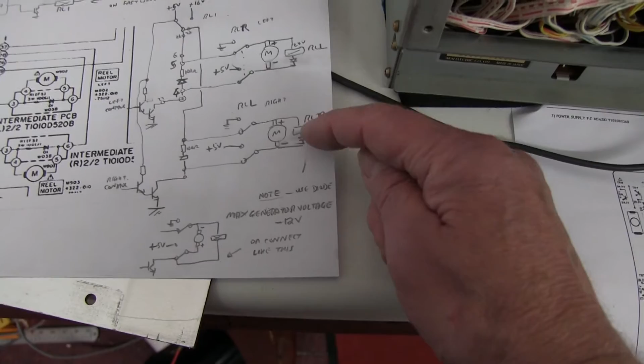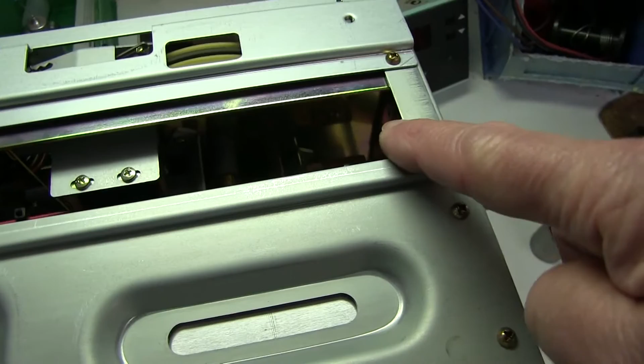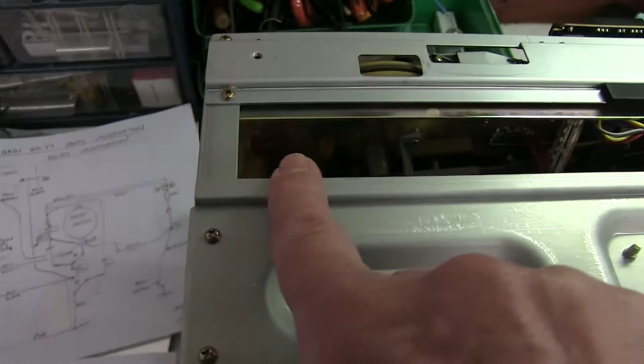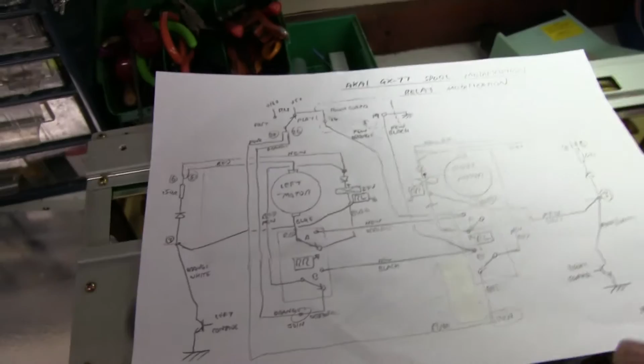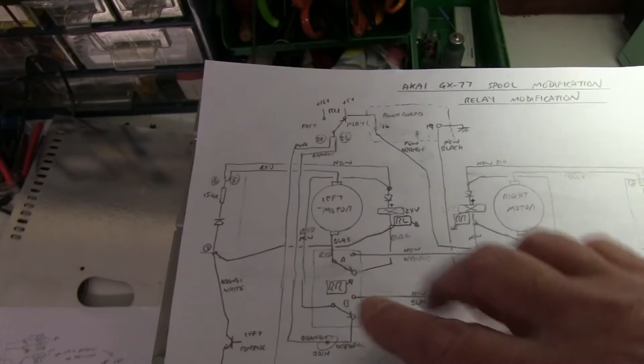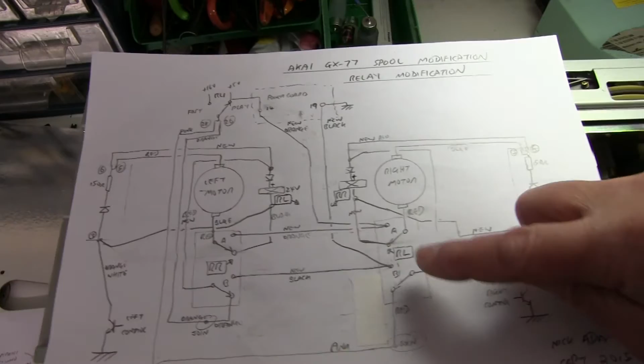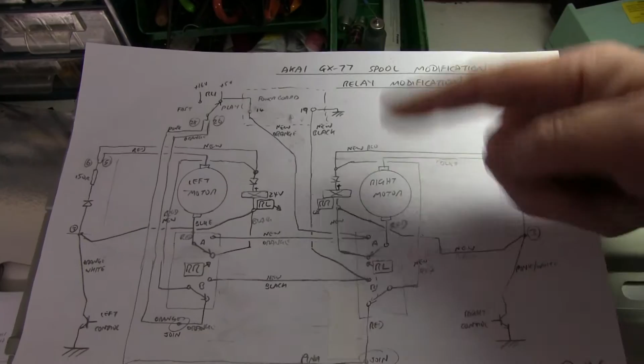The relays operate on the high voltage spool side and operate the contacts on the other motor. Because you operate one relay on the fast spool but want to do the connections on the slow spool, that's why you have all these wires running across. So I've drawn a diagram - if you follow it meticulously, it's very straightforward. It looks like a mess of wiring, but all it is, is one relay here operating the contacts on the other motor, just swapping the voltages around.